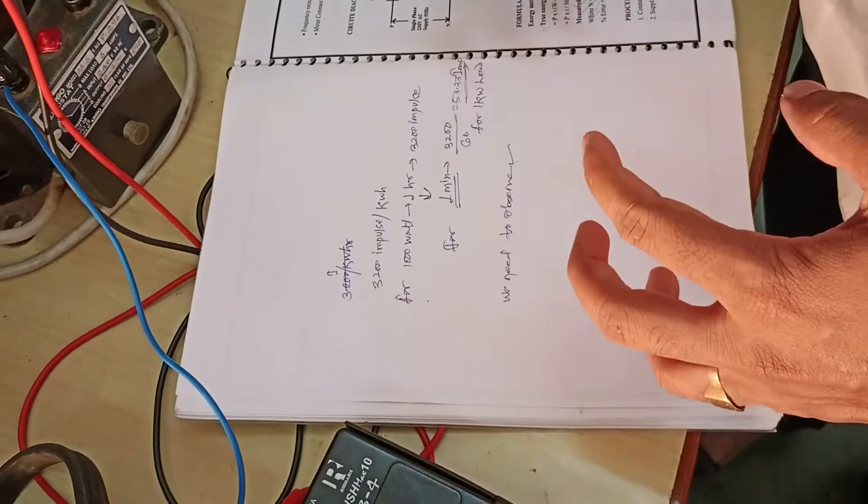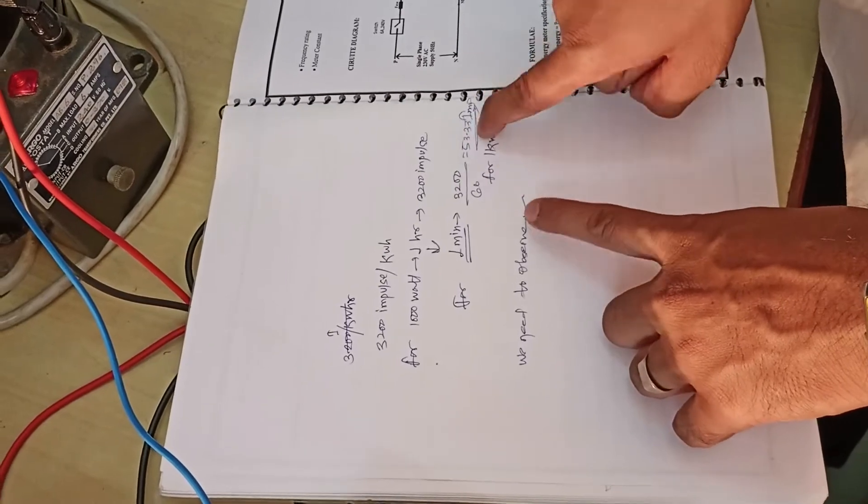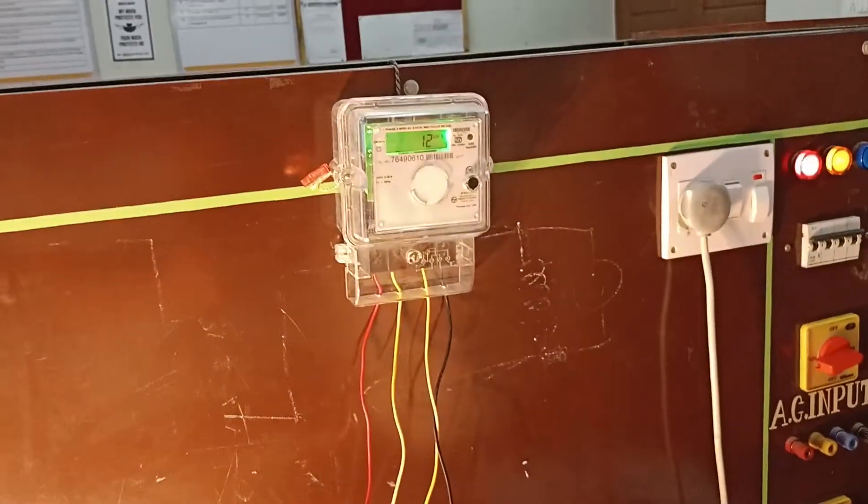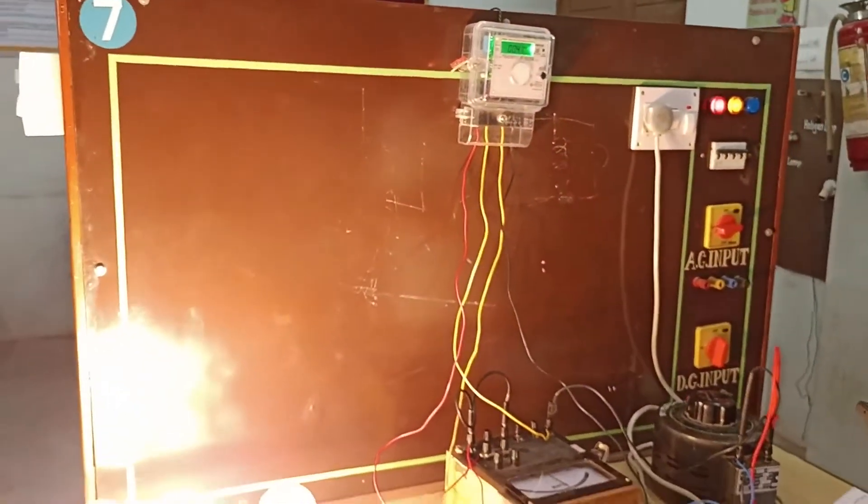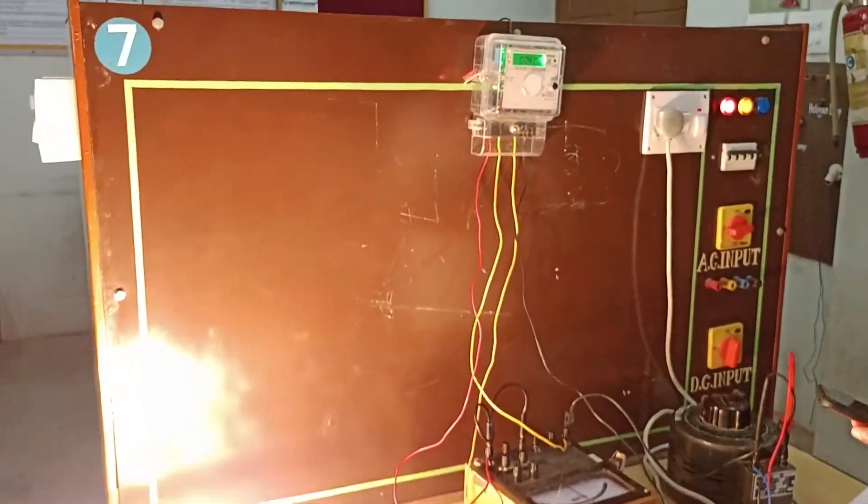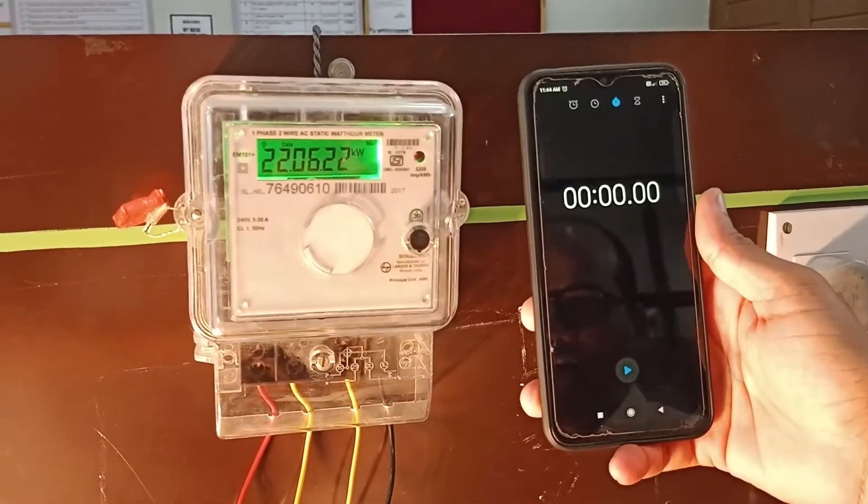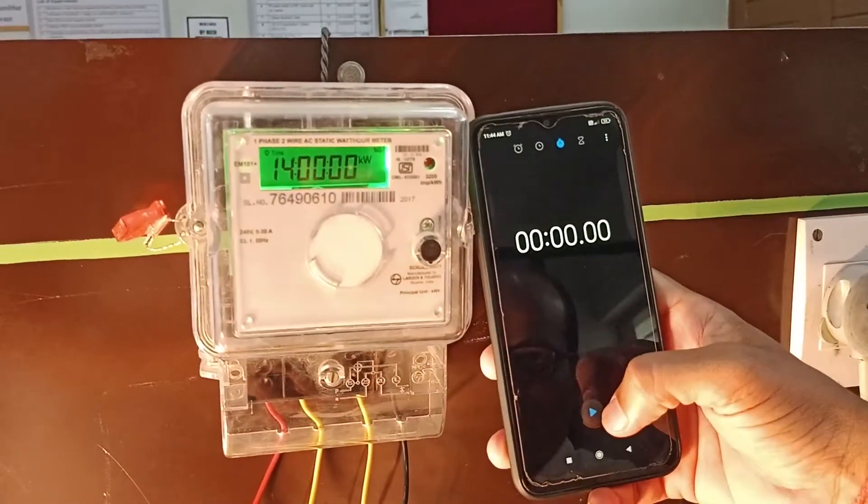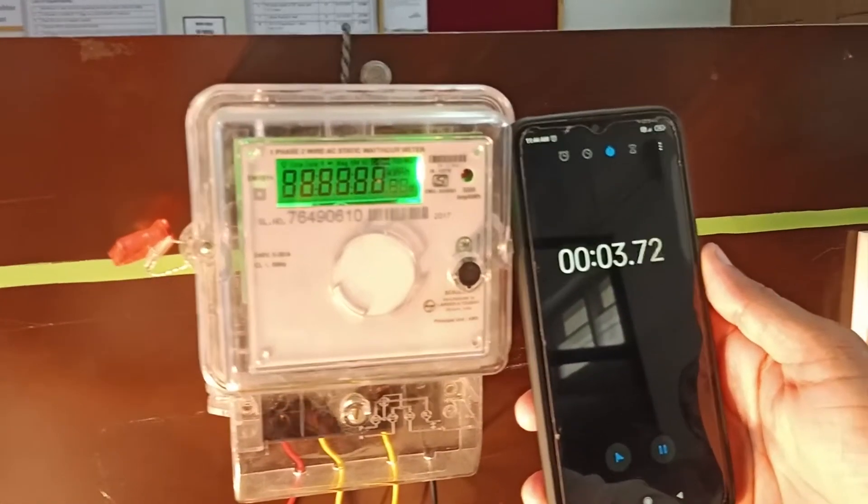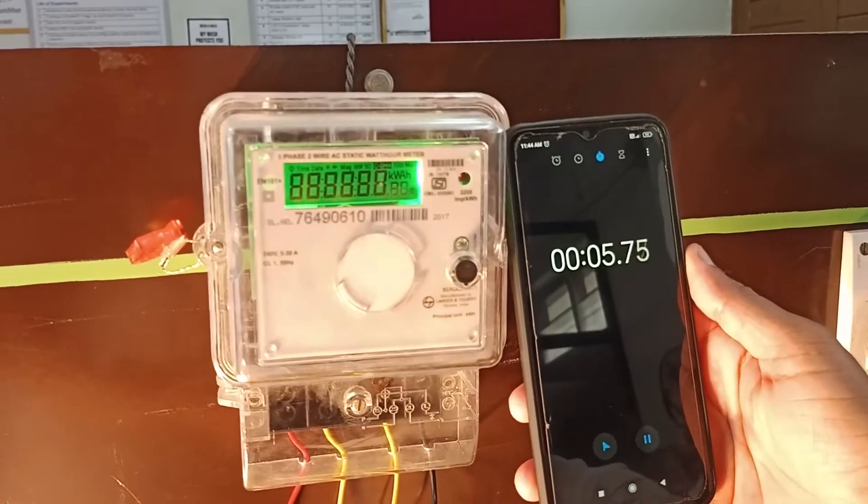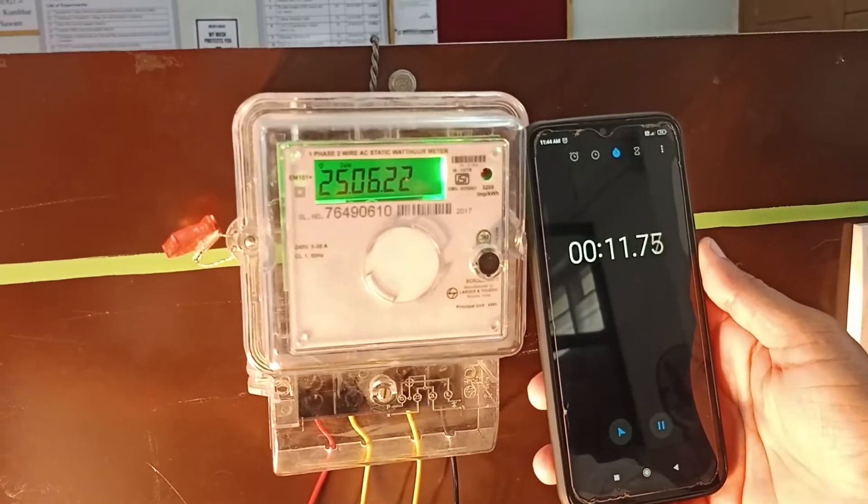This is the theoretical value. For calibration we are verifying if this theoretical value of 53 is matching to our practical load or not. For that I will simply start my stopwatch. I have started my timing and we're going to calculate how many impulses occur.